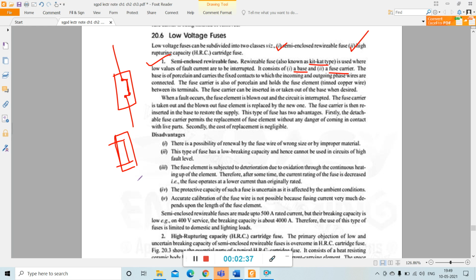So the base is of porcelain and carries the fixed contacts to which the incoming and outgoing phase wires are connected. The fuse carrier is also of porcelain and holds the fuse element, which is tinned copper wire, between its terminals. So these two are terminals, and between these terminals is the fuse element connected here. The fuse carrier can be inserted in or taken out of the base when desired. When a fault occurs, the fuse element is blown out and the circuit is interrupted. The fuse carrier is taken out and the blown out fuse element is replaced by a new one. The fuse carrier is then reinserted in the base to restore the supply.